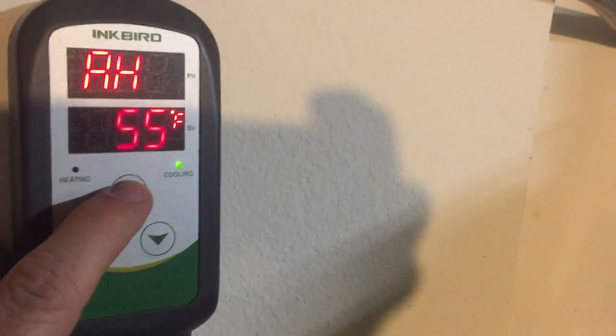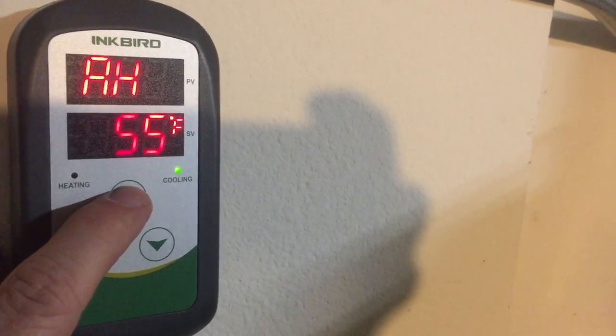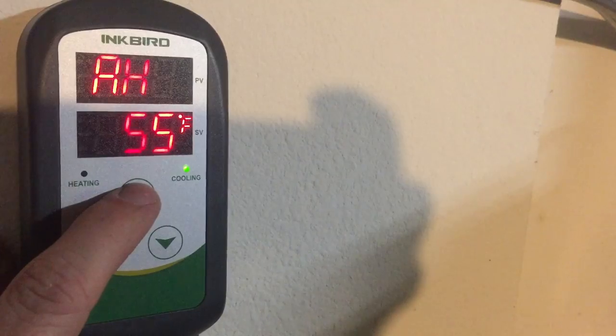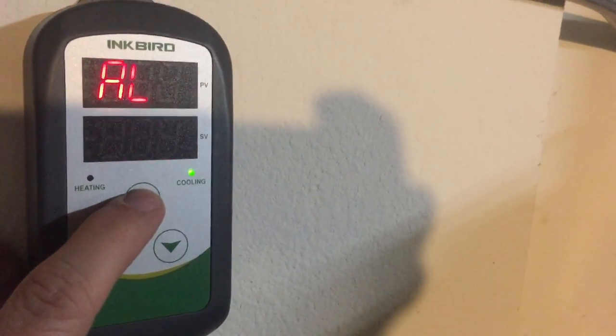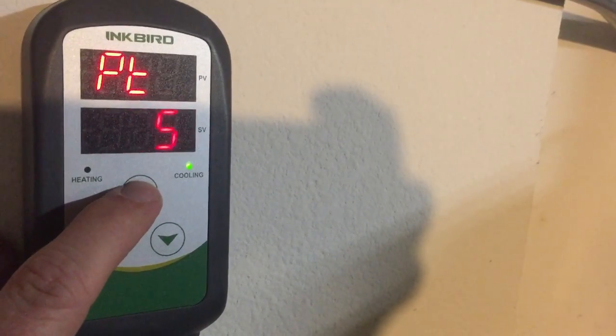The AH, that's the alarm high. I have it set at 55, so this will alert me if this thing goes above 55. The alarm low, I want to be alerted if it goes below 29. That's freezing the meat now.